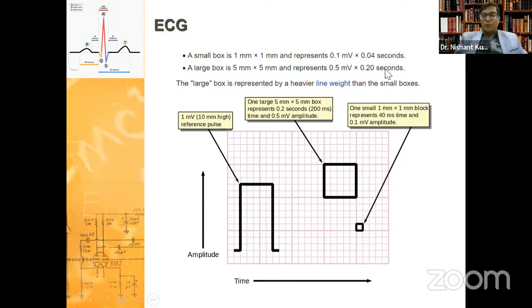Now, something about the paper. This is also very important, and I'll relate an interesting incident behind it. Now, we know that this is the ECG paper, everyone has seen it. It has some small squares and large squares. So the small square is 1 mm and a large square is 5 mm by 5 mm. Now, the paper which runs through the machine is always 25 millimeters per second. That is, in 1 second, you'll have 5 of these boxes which will run through the machine and a tracing will be obtained. So that makes 1 mm represent 0.04 seconds. So each small box represents 0.04 seconds and a large box represents 0.2 seconds. Naturally, 0.04 seconds into 5 is 0.2 seconds. 0.2 seconds into 5 is 1 second. So 25 mm per second.